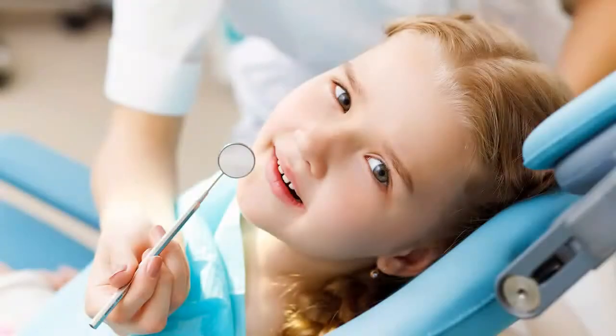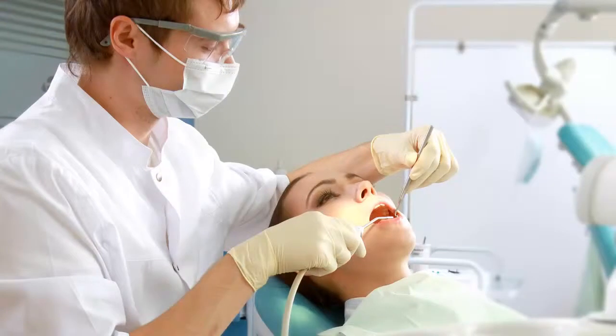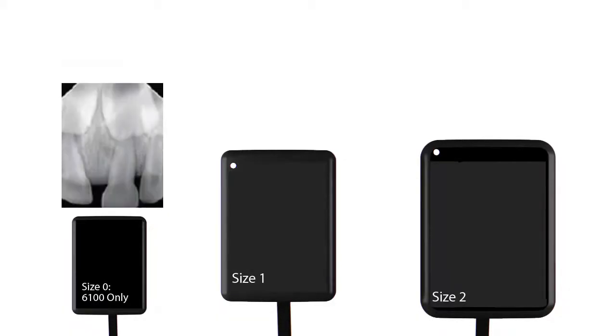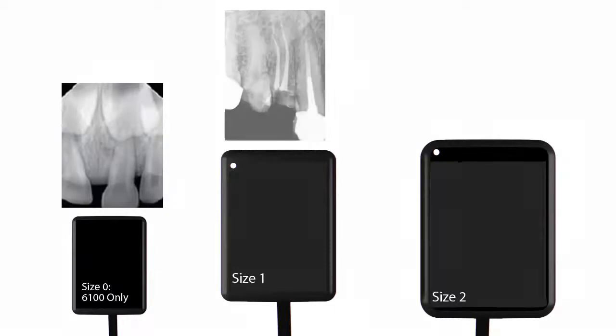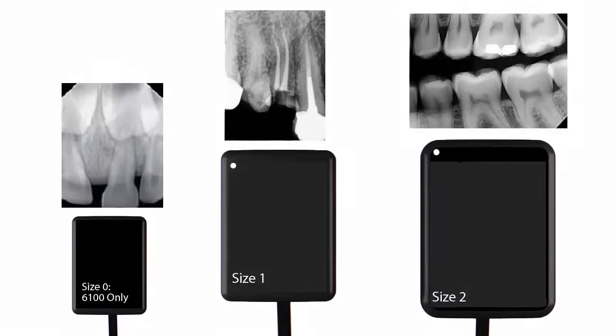Patients come in different sizes, and so do RVG sensors. RVG sensors are available in three sizes: 0, 1, and 2. All of the sensors have rounded corners for patient comfort. Size 0 was designed for pediatric examinations. Size 1 serves as a general-purpose sensor and is perfect for vertical images. Size 2 is used primarily for the acquisition of bite-wing images and periapicals.